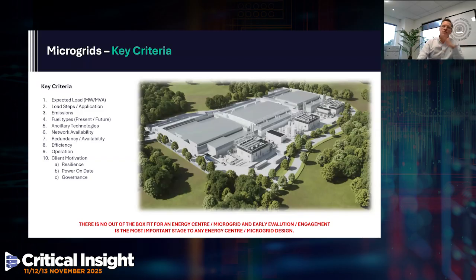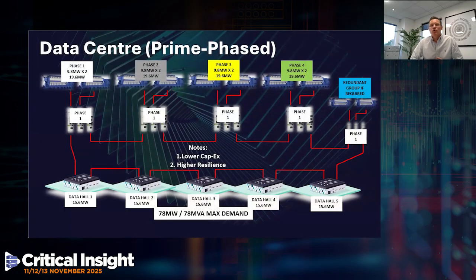If you build a 100 MVA microgrid in island mode and you only have 1 MVA of load, it's not a good engineered solution. So just to give you some ideas, we've got a phase system. In the initial phase we put in 19.6 megawatts, phase 2 another 19.6, delivered in phases for each data hall. Rather than asking for 200 megawatts of power, we deliver these in phases.